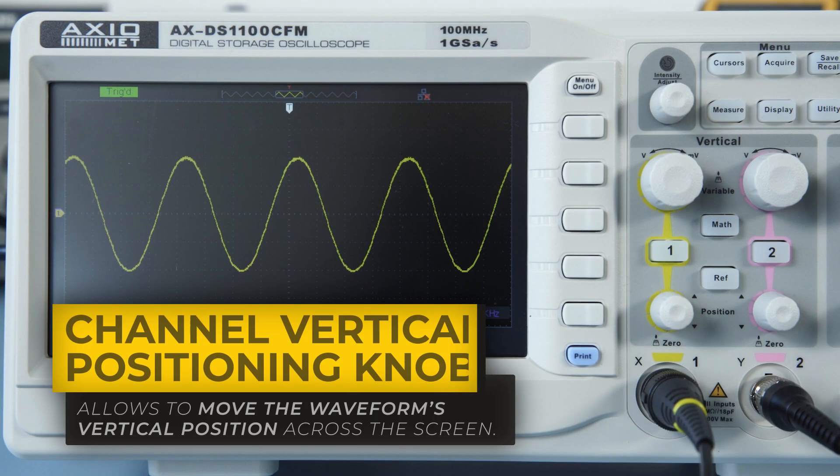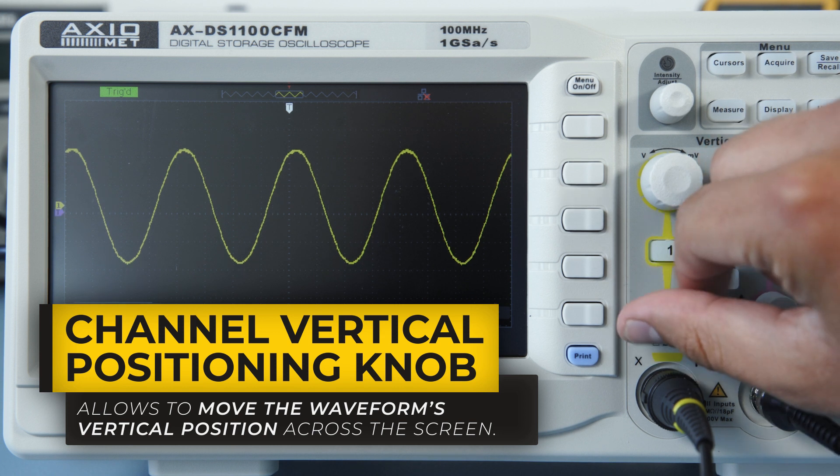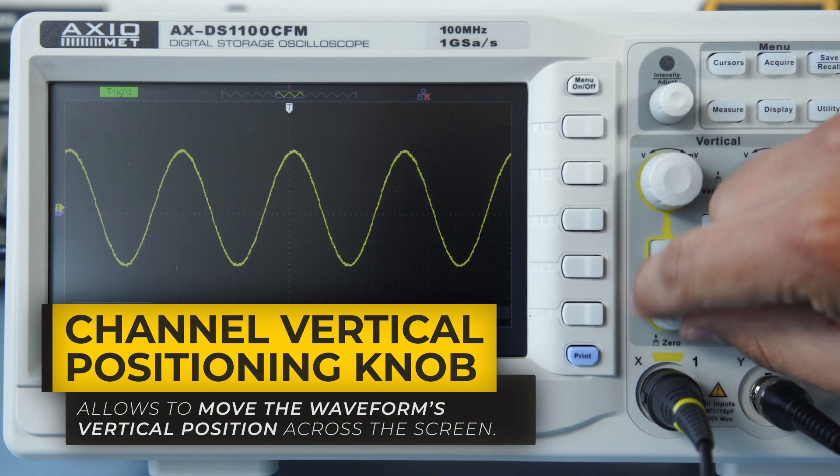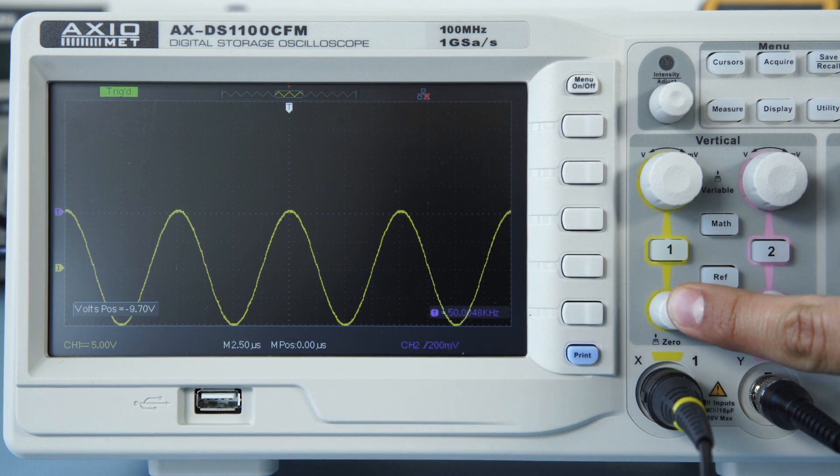To move waveforms vertical position across the screen, use the vertical positioning knob. To return the waveform to zero, simply press the knob.